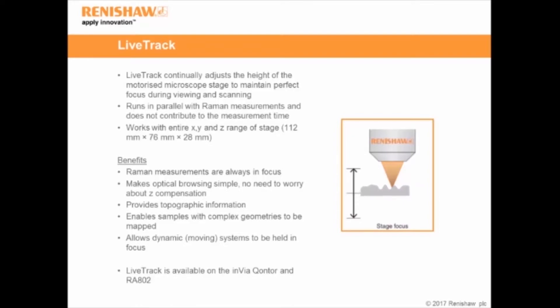LiveTrack runs in parallel with Raman measurements and doesn't add any extra measurement time. It works over a large area, so we can use the whole XYZ stage range. Our Raman measurements are always in focus, so we always get the best performance from them. It also works in optical browsing mode, so you can look at the sample under the microscope and it automatically maintains the Z position as you scroll around. During measurement, we read out the position of the Z stage, enabling us to get information on the sample topography, which we can overlay with the Raman image to provide more information.